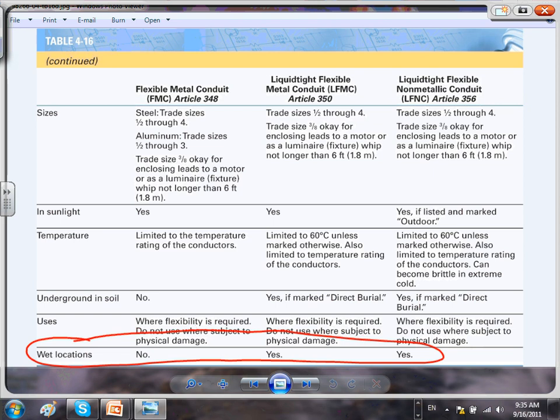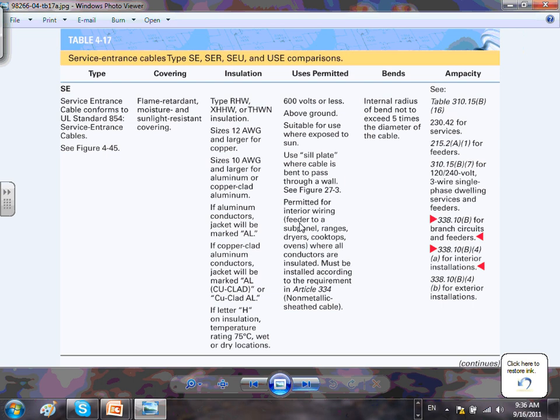Any questions? MC cable always comes with the ground conductor — always. So when using cables, grounding is not an issue. We're talking about flexible conduits specifically. Some people, instead of using flex to tie to equipment, use an MC cable — no problem. You grab an MC cable and tie it to the equipment; it gives you some flexibility. Let's take a break.